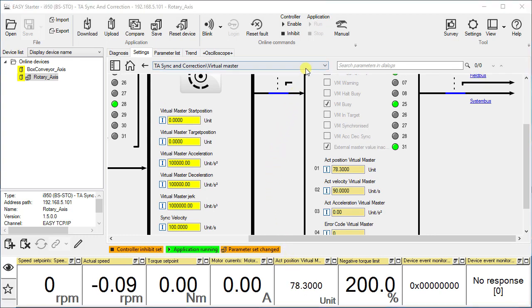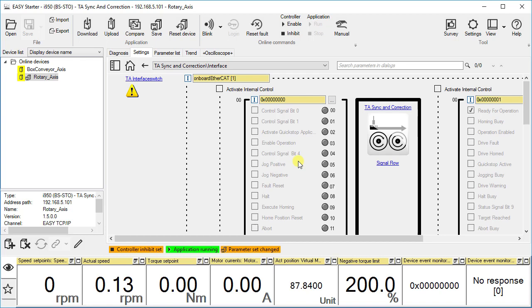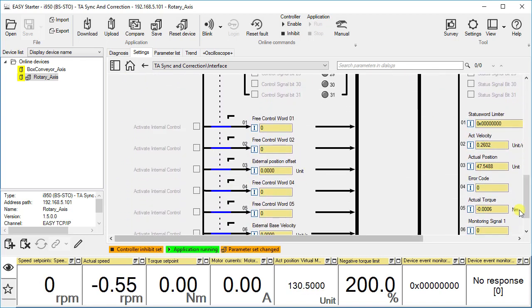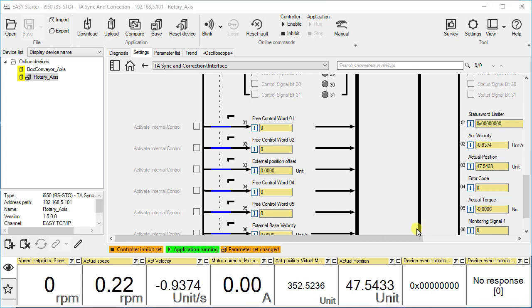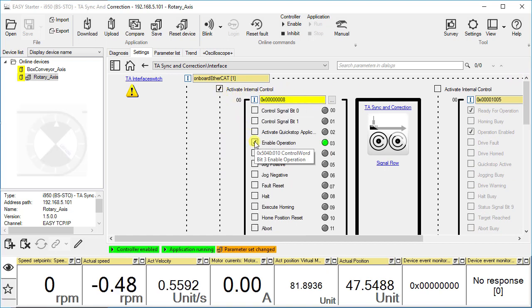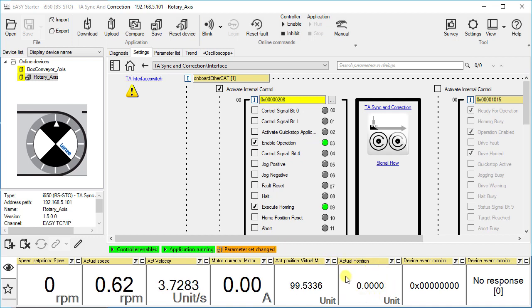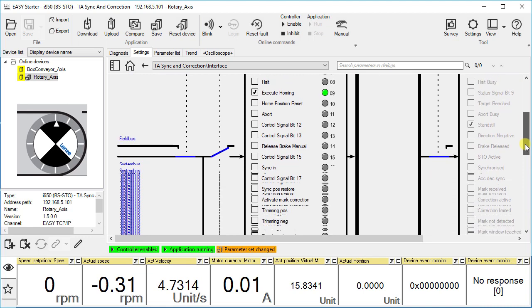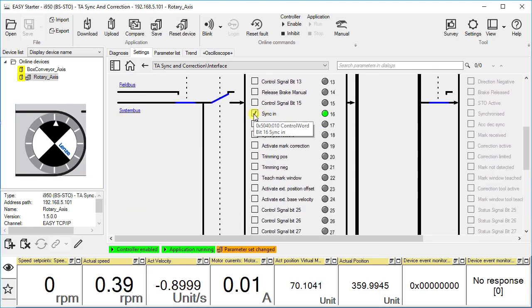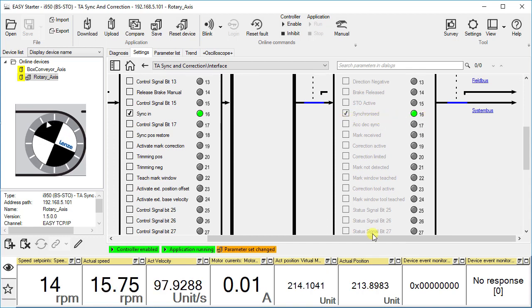Now we will sync the real axis with the virtual axis. From the dropdown select the interface of the TA. Before we enable the operation, we additionally place the actual position and actual velocity in the monitor area. Check the box of activate internal control. Select enable operation to enable the drive and execute homing once. Our actual position changes to the home position. Enable sync in to synchronize the virtual axis and real axis. From the current position, current velocity and the status signals, you can see that the real axis is synchronized to the position of the virtual master and follows the master value — that is 90 units per second.